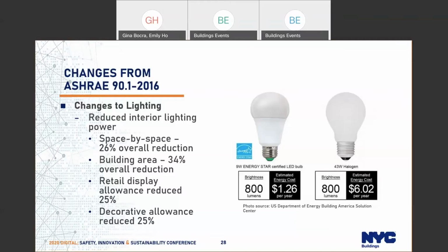These estimates of reduction come from the Pacific Northwest National Lab, and they're area weighted based on construction within the US. So it's not a flat reduction in interior lighting power. You'll see some spaces reduced maybe by 50%, others didn't reduce at all. But overall, if you're looking at a weighted average of construction, they reduced under the space-by-space method by 26%. Under the building area method, there's an overall reduction of 34% in lighting power density.